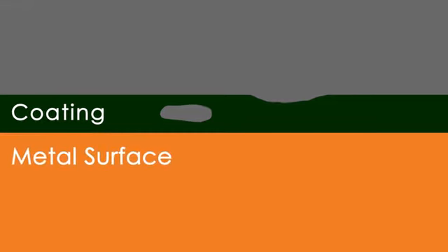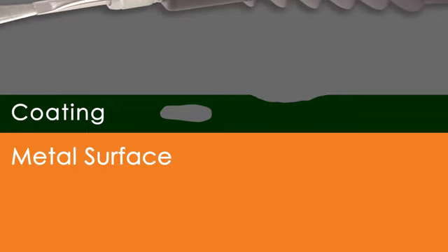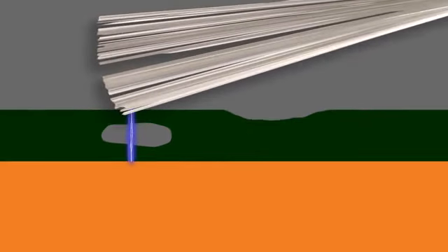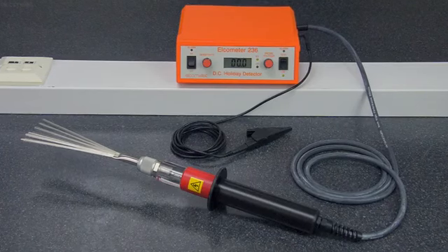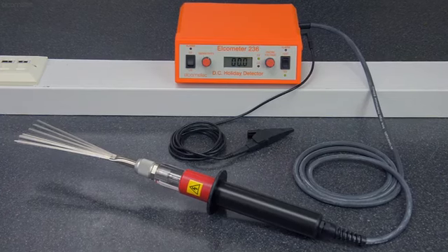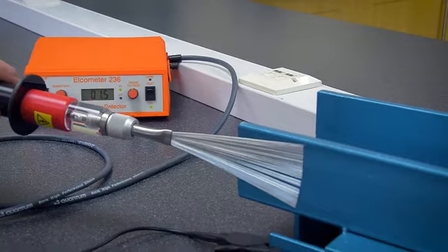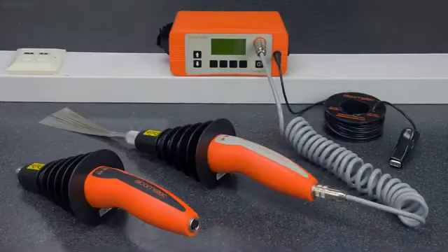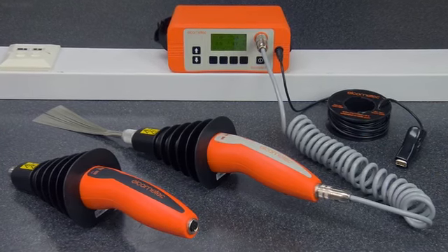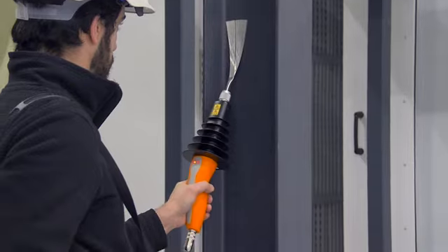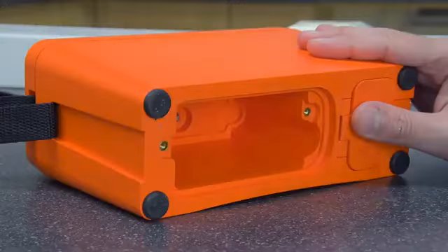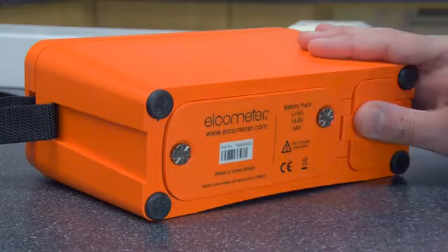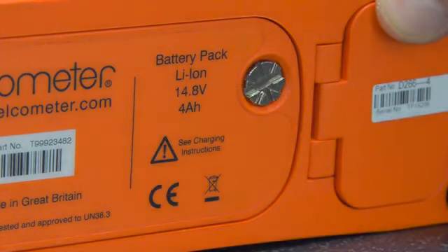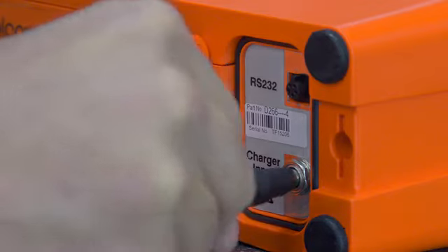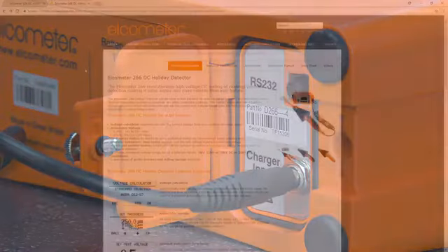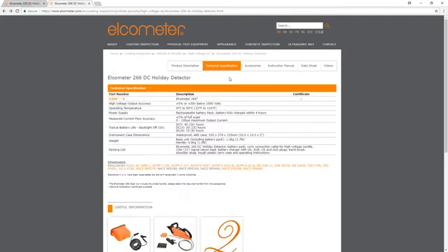As the high voltage method can locate any area where the coating is weaker than specified, this allows you to detect flaws that don't go all the way down to the substrate, as well as voids within the coating. Elcometer has two continuous DC detectors, the Elcometer 236, where the high voltage supply is generated within the instrument and sent to the probe handle via a high voltage cable, and the Elcometer 266, where the high voltage supply is generated within the handle and connected to the instrument via a low voltage cable, resulting in a safer way to test for flaws. The gauges are powered by their own rechargeable battery that deliver 8 to 40 hours of continuous use, depending on the gauge being used and the voltage being tested with. We recommend charging the battery fully before starting to ensure uninterrupted testing, and there are full details of the typical life of the batteries on the Elcometer website.